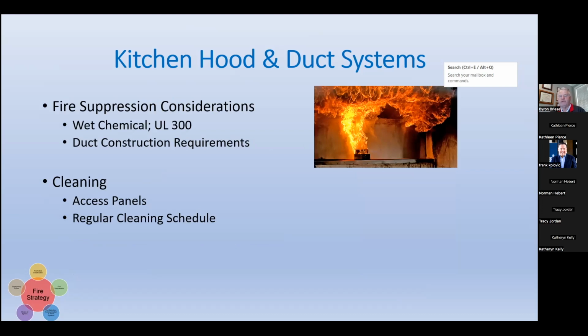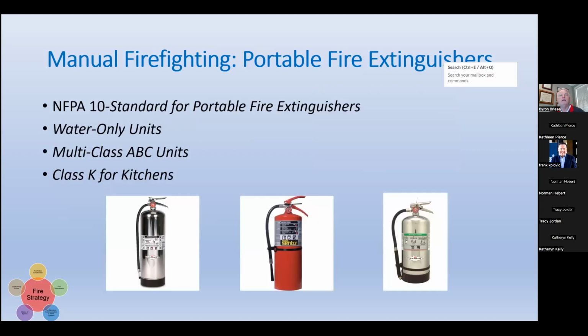So UL 300 is the key standard for all of your suppression systems in your kitchen. You can read that on the storage bottles that typically hang on the ceiling, or you can check with your maintenance firm. If you don't have a maintenance firm, you should get one. And the final area, particularly on kitchen fires, is that you want to be sure you're using a Class K extinguisher in the kitchen areas to handle those grease fires. Water-only units won't work, and the ABC units not only won't work, they'll also make a complete mess. So we go to the Class Ks with training.